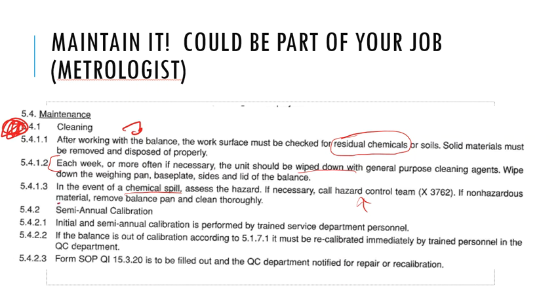Next, this company is requiring a semi-annual calibration. So this would be a more full-blown external calibration used on the analytical balance to make sure that it's continuing to work the proper way. Next, the initial and the semi-annual calibration should be performed by trained service department personnel. All right, that is just a confirmation to say, leave it to the professionals, right?